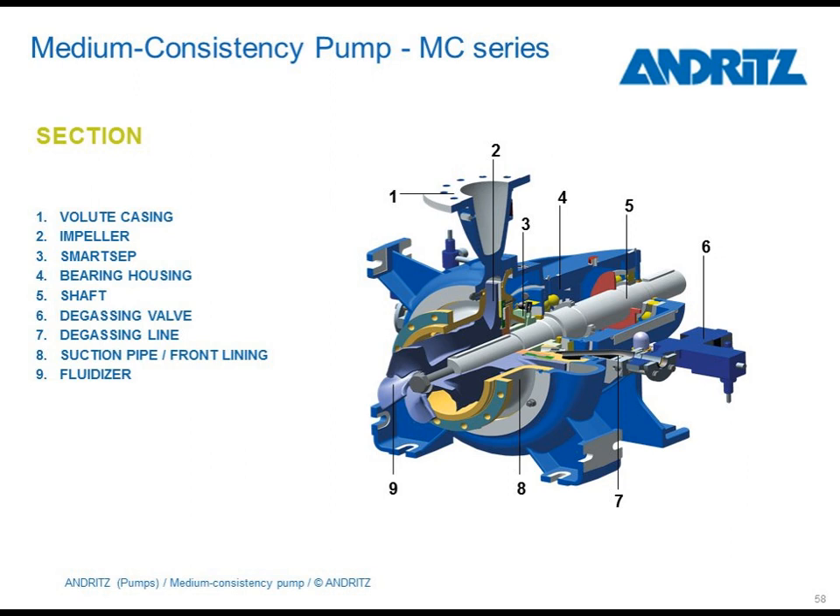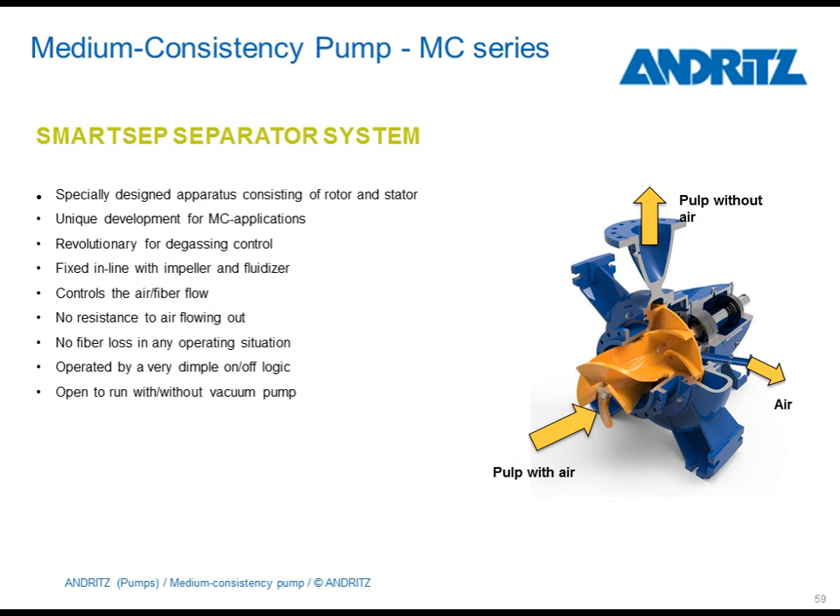Main parts of the MC pumps are the same as for any other process pump, such as volute casings and impellers. But in addition, there is also a fluidizer to fluidize the pulp suspension. Just remember the picture shown by Jussi of a man standing safely on a pulp suspension of only 10% — we are pumping suspensions up to 16%. To handle the air content in the suspension, our pumps are also equipped with a SmartSep system. This SmartSep system ensures proper degassing and prevents any fiber loss. Due to that, the pump design can focus on high efficiency and vacuum-pump-free operation becomes possible as well.